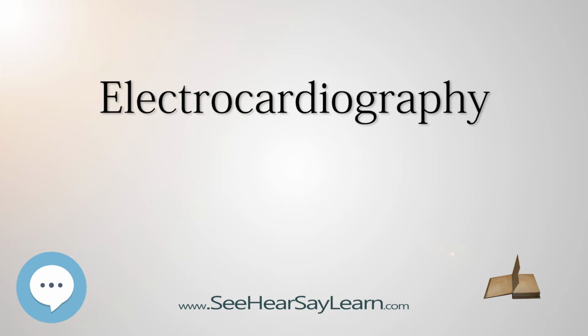Two common electrodes used are a flat paper-thin sticker and a self-adhesive circular pad. The former are typically used in a single ECG recording while the latter are for continuous recordings as they stick longer. Each electrode consists of an electrically conductive electrolyte gel and a silver/silver chloride conductor. The gel typically contains potassium chloride, sometimes silver chloride as well, to permit electron conduction from the skin to the wire and to the electrocardiogram.